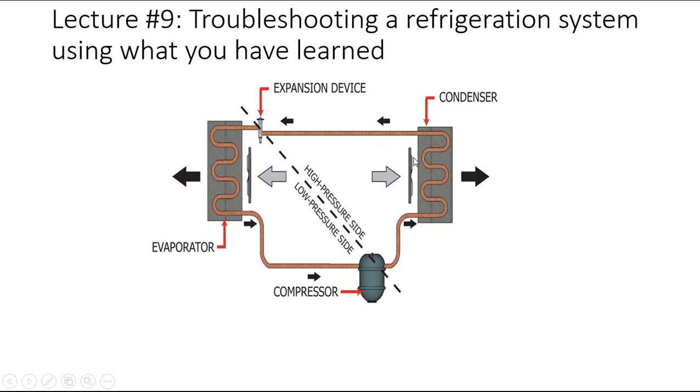On the condenser side, same thing. Generally you'll have a condenser located outdoors. Condensers are usually simpler to see if they're clean or not. Make sure that this inlet surface is clear—no leaves, debris, or cottonwood tree. If you check those two things, especially in the spring at the beginning of the season, you're going to probably be a hero. That will solve most of your problems right off the bat.